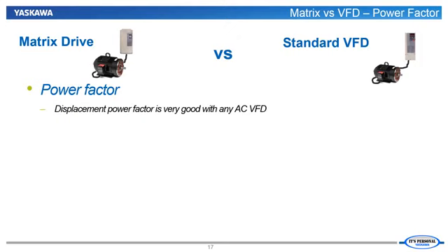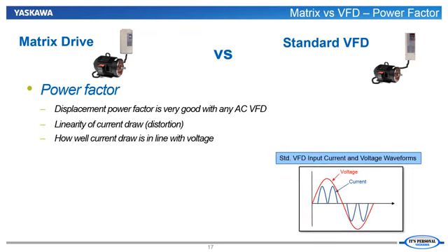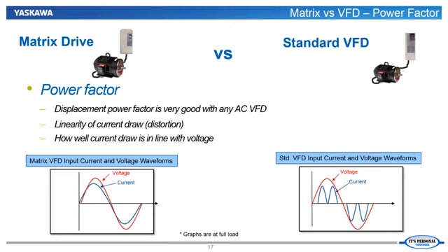What makes a standard VFD have better power factor than an across-the-line motor is that the displacement power factor is so much better when a VFD is between the induction motor and the line. Now that our comparison involves drives in both cases, displacement power factor is not really a differential. This time the differential comes from how much current distortion is created. Standard VFDs draw nonlinear current. In other words, the current is not drawn in line with the voltage. The greater the current waveform differs from the voltage waveform, the larger the current distortion. The true downside of the harmonics created by this distortion is that they also cause extra heating in the cables and devices that are supplying the VFD with power, without any real benefit. In the left-hand figure for the matrix drives, you can see that both the displacement power factor is very good and the current distortion is very minimal.